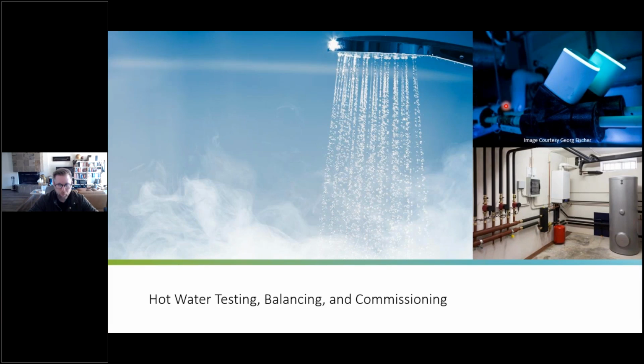Now, an important part of the hot water recirculation system strategies from a practice standpoint is making sure that the system is tested, balanced, and commissioned. We're going to touch a little bit on balancing valves in a little bit, but one of the things that I think we're going to see an advent of, especially at IAPMO, where we're involved with a lot of standards creation, is some product testing here in the near future for automatic balancing valves, so thermostatic, pressure independent, specifically for domestic hot water applications, and then electronic types.